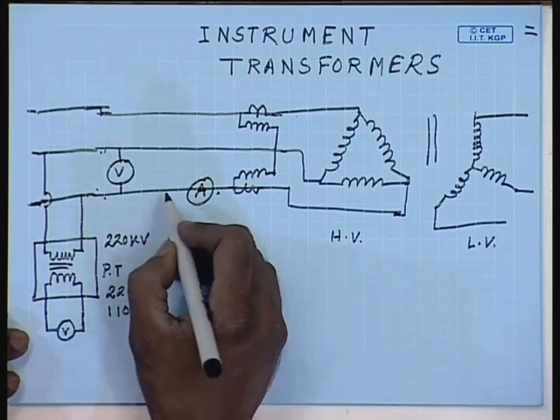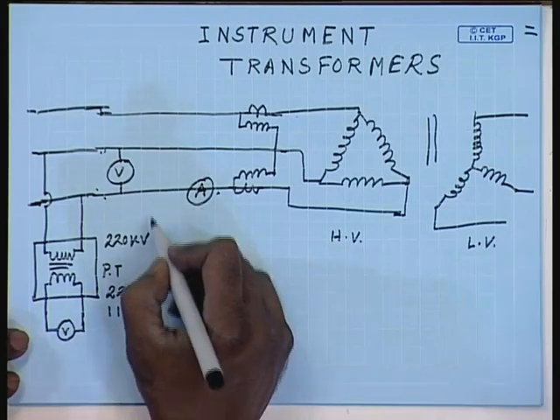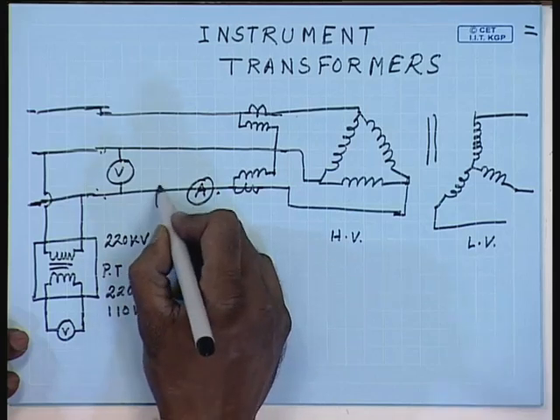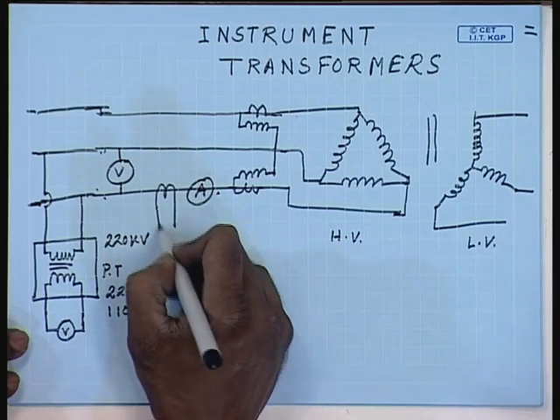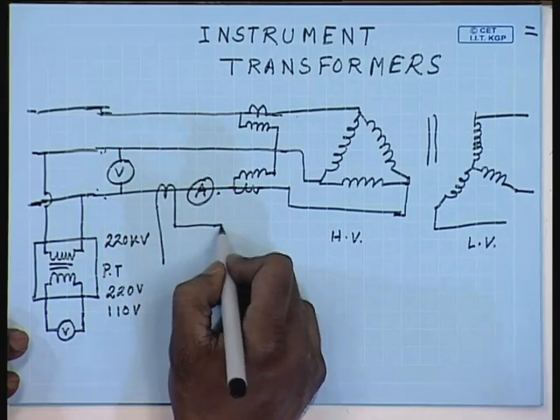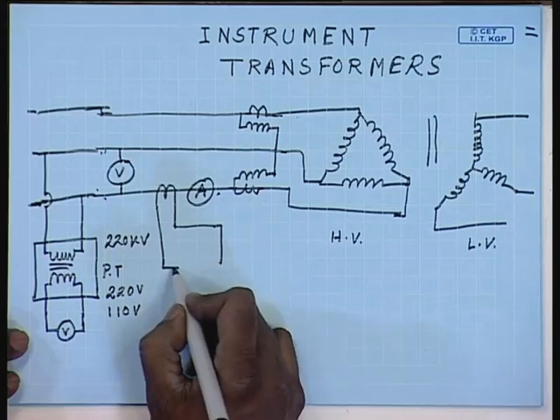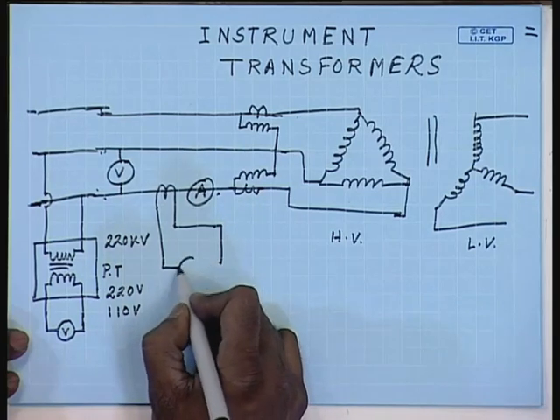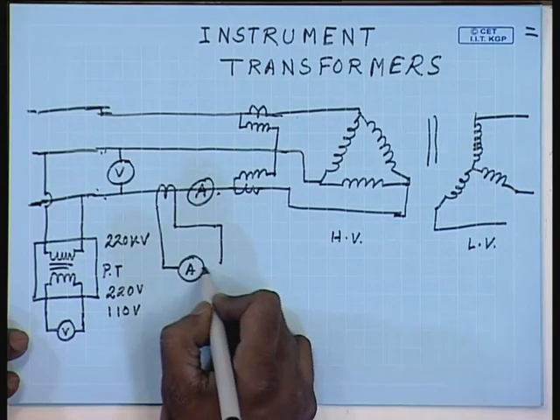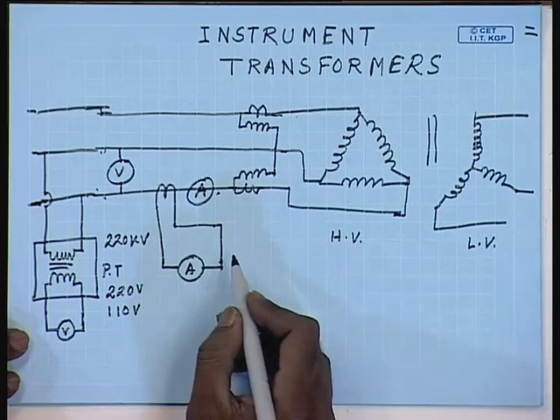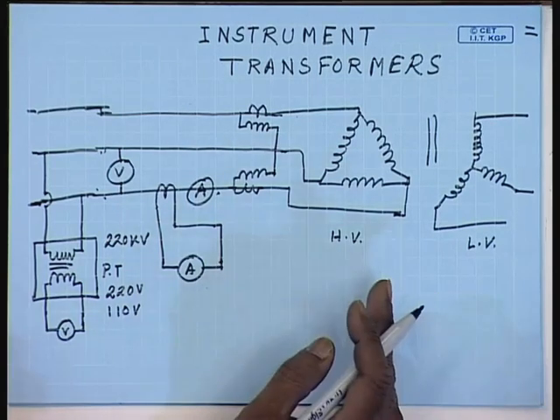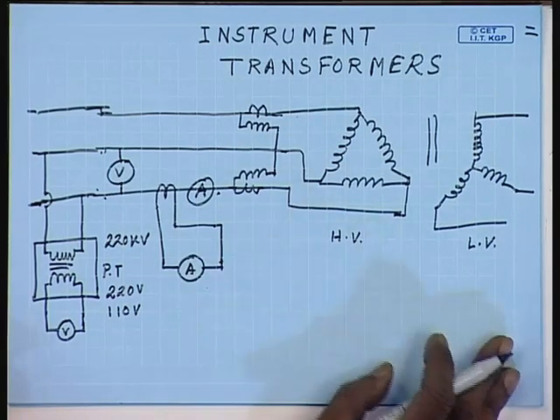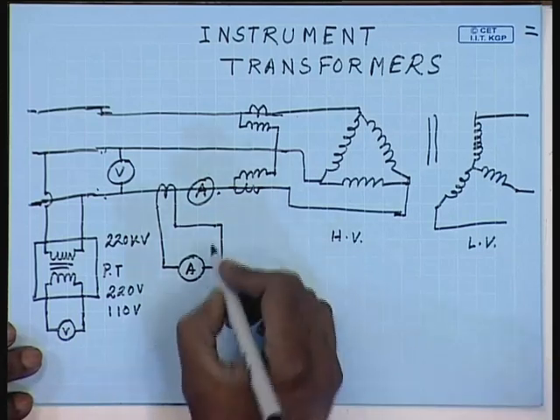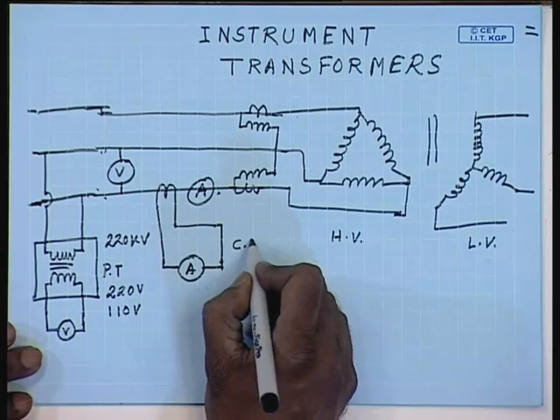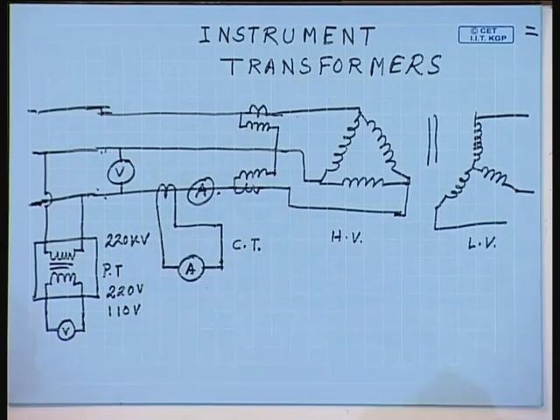And a current transformer steps down the current, to which an ammeter can be connected, to a much lower value, with a ratio of 100 or even more. So, this is called the current transformer, or in short the CT.